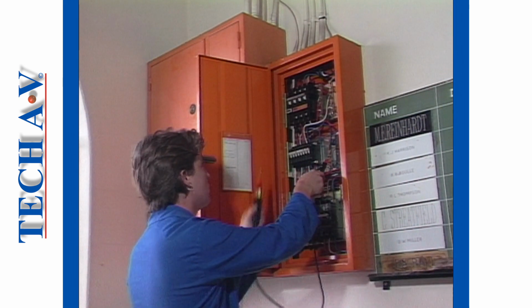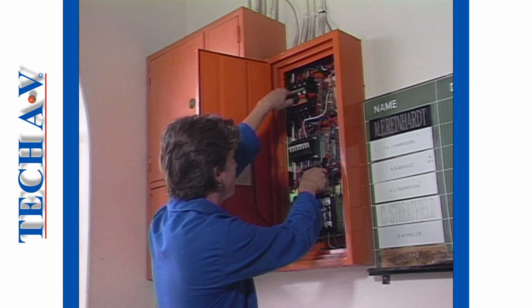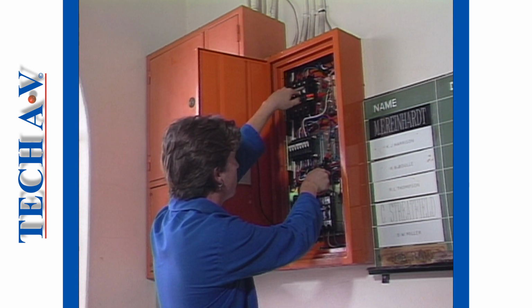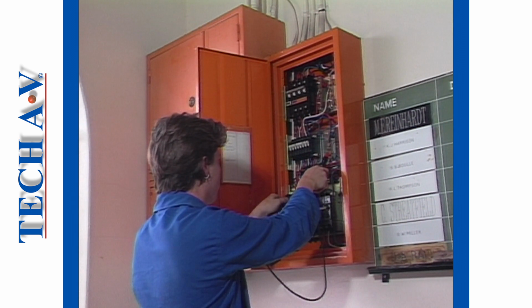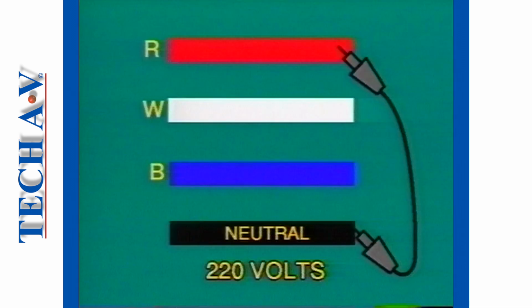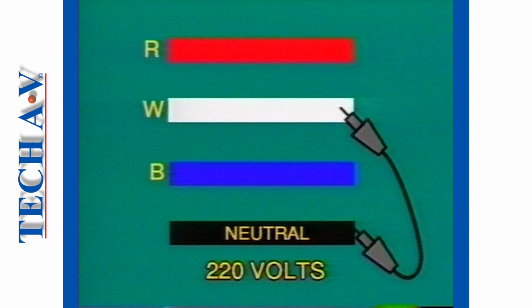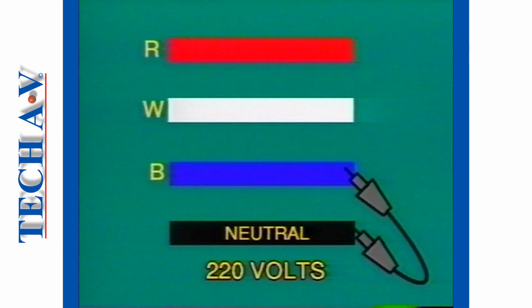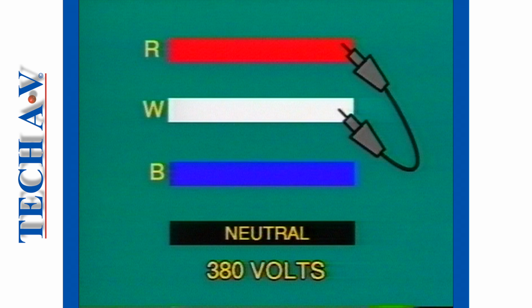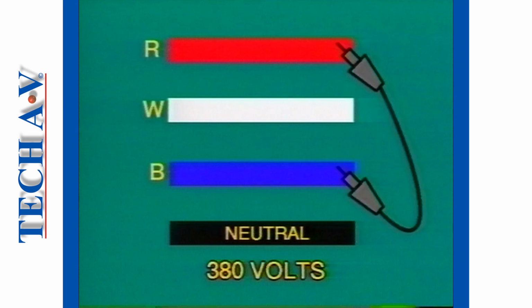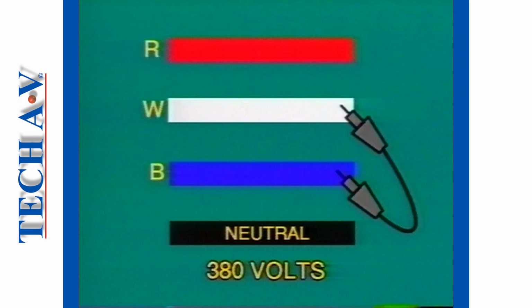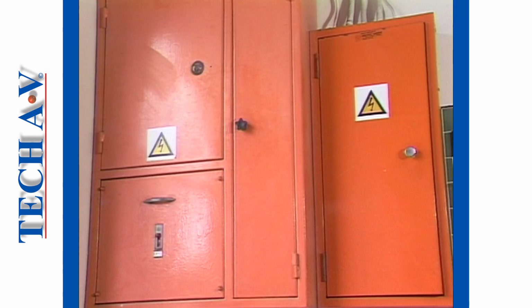The instrument may also be used to check three-phase supply, which employs the 4-wire system. In such a system, there are 3 live phases and 1 neutral. Testing between any live phase and neutral should yield a reading of 220 volts. However, testing between phases, that is between red to white, red to blue, or any combination excluding neutral, you should obtain a 380 volt reading. On no account should you test distribution board circuits unless you have received the necessary training.